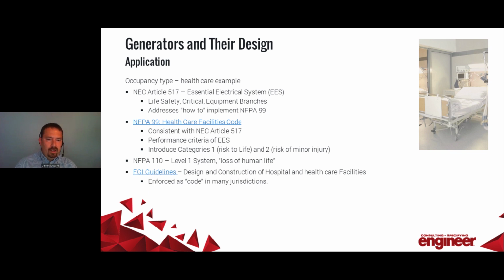NFPA 110, again, has a Level 1 description of a system that has a risk of loss of human life. So your hospitals would be defined as a Level 1 system per NFPA 110. And then in healthcare occupancy, you often have FGI guidelines to contend with as well. Many local jurisdictions enforce it as code. So it's important that in addition to the national codes, the local amendments, and the standards, you also follow FGI guidelines in a healthcare facility as well.